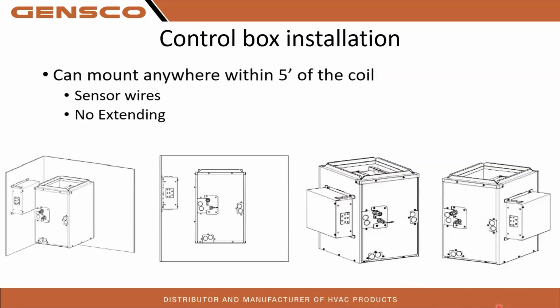Control box installation. The control box that comes in the kit, the bare metal box, can be mounted anywhere within 5 feet of the coil. The reason we're limited to 5 feet is because our coil sensor wires are attached to the coil. There's only about 6 feet of wire on that, and you want a little bit of slack, and we cannot extend those sensor wires. They cannot be spliced, otherwise you're going to end up with coil sensor errors.